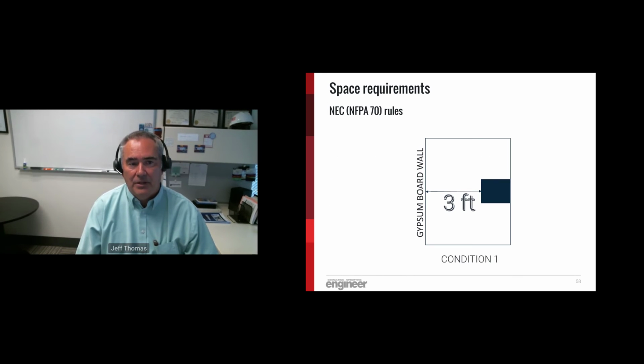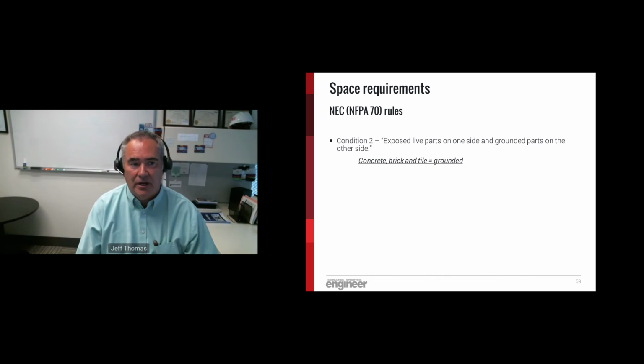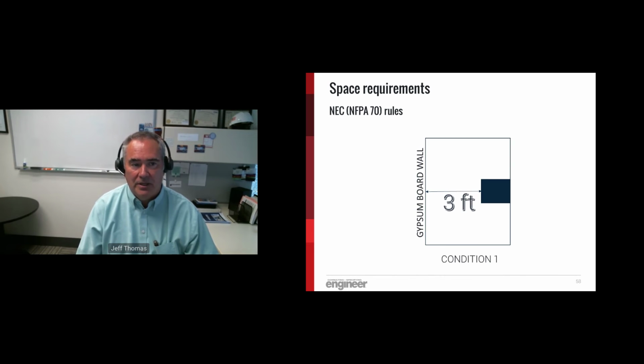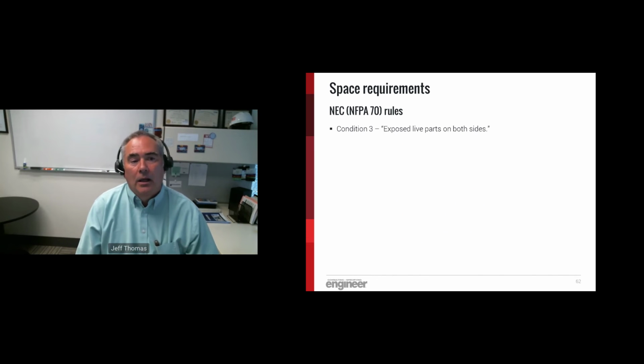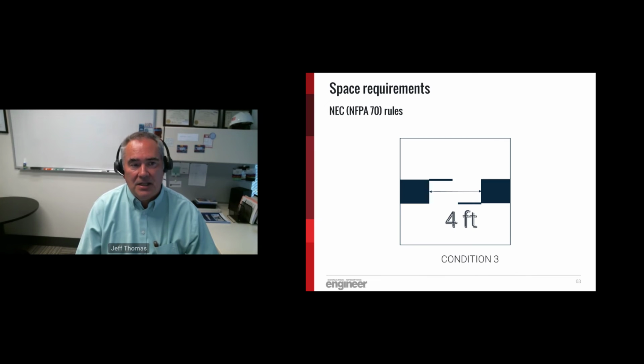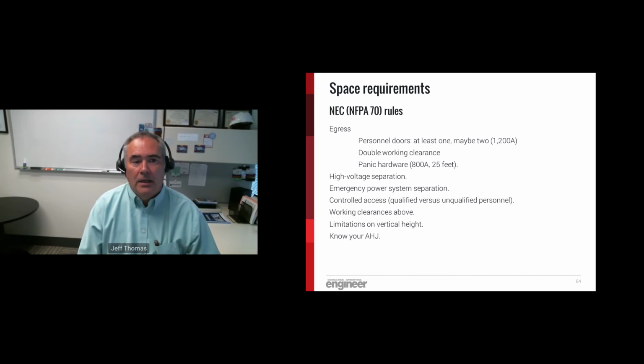I'm going to fly through these. Basically, 3.5 feet is your friend. I know 3 feet is the minimum, but go with 3.5, and then you're always safe unless you're going to deal with medium voltage. One thing to be careful of here is NEC characterizes a brick, block, or tile wall as a grounded surface. So that kicks you into the 3.5 feet space. Keep that in mind.